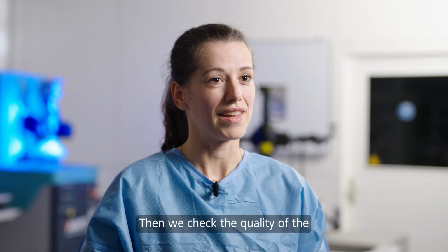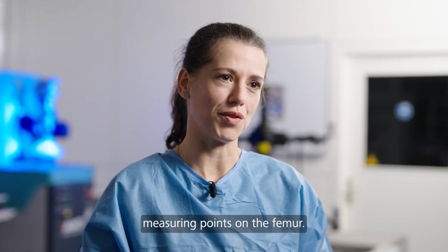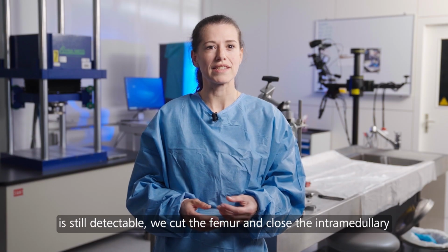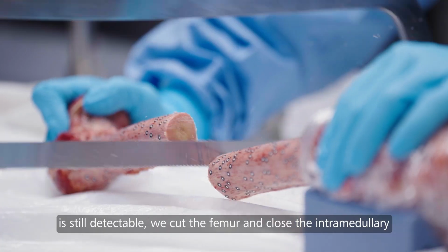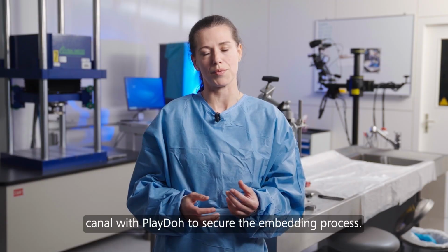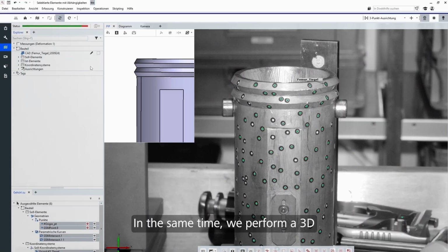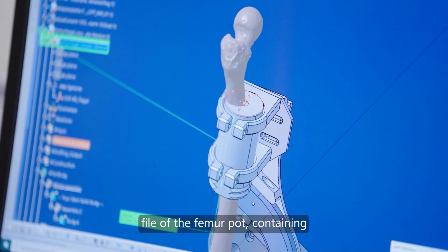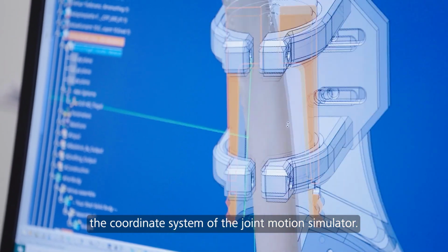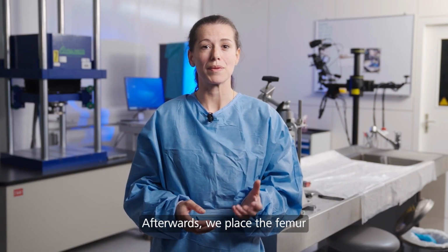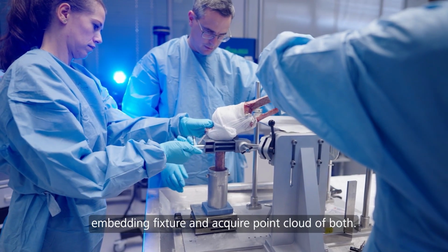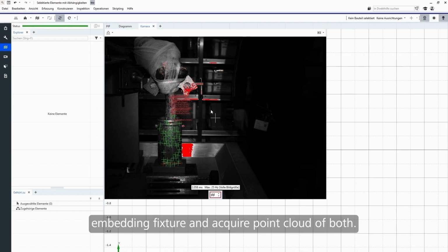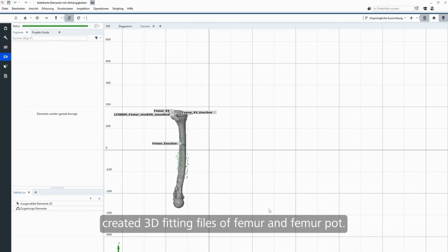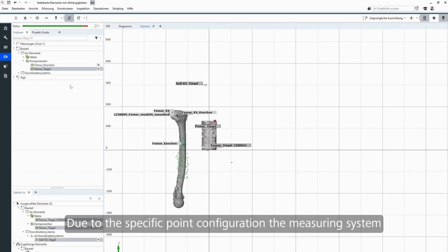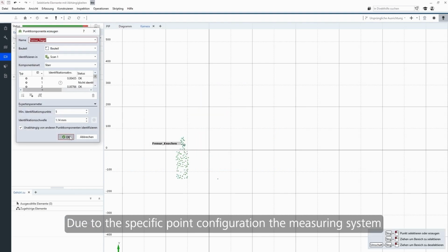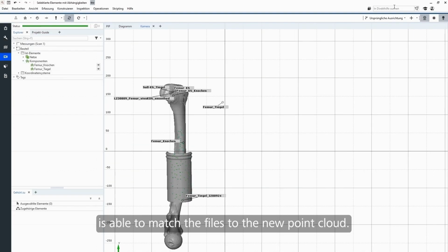Then we check the quality of the measuring points on the femur. If the specific point configuration is still detectable, we cut the femur and close the intramedullary canal with Play-Doh to secure the embedding process. At the same time, we perform a 3D fitting of the femur pot and the CAD file of the femur pot containing the coordinate system of the joint motion simulator. Afterwards, we place the femur together with the femur pot in the embedding fixture and acquire a point cloud of both. Then we insert the previously created 3D fitting files of the femur and the femur pot, and due to the specific point configuration, the measuring system is able to match the files to the new point cloud.